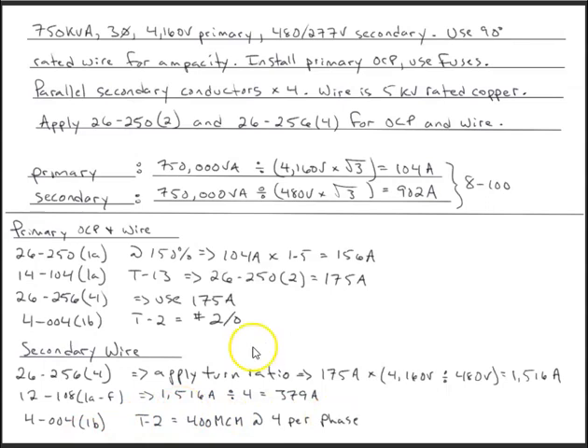So just to recap, we're calculating for the primary overcurrent protection and wire. Notice that there is no overcurrent protection on the secondary in this case. So another thing to be aware of, and where I have issues with students, is sometimes a student will stick some overcurrent protection in the secondary. But notice this first part of the calculation is the primary overcurrent protection and wire, so the primary OCP and the primary wire. That's what's going on here. Notice there's more calculations going on here.